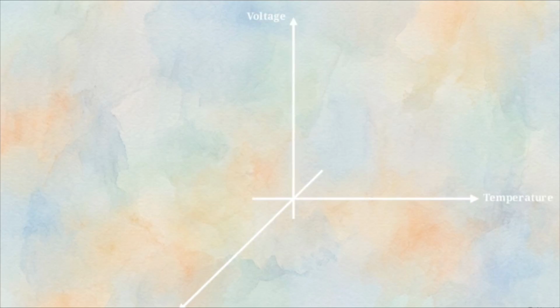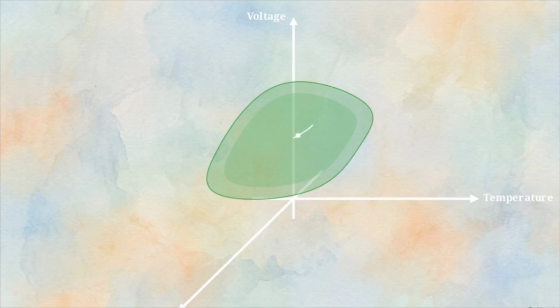Cell manufacturers define exactly what that safety envelope looks like. This 3D Cartesian graph plots the three critical operating axes of any lithium-ion cell: voltage, temperature, and current. The smooth, curved volume in the center represents the cell's baseline safe capability. If a charging source forces the cell's voltage past its maximum threshold, the electrical pressure damages the internal structure.